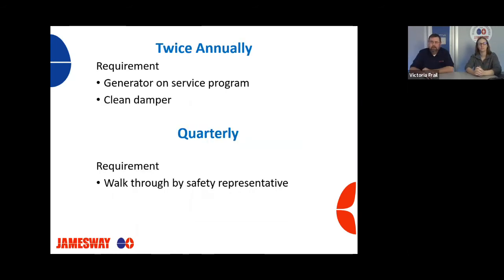Twice annually, I want the generator to be on a service program with a generator company. That's what they do. That's what they know. It's more than just a truck motor. There's a lot of different things on there. Yeah. And the same really applies to your ventilation equipment. You should have that on a twice annual service program, usually one in the fall to check your heating system before you start it up, and one in the spring to check your cooling system before you start that up. Absolutely, I agree. Clean dampers on the generators and on your air conditioner units.